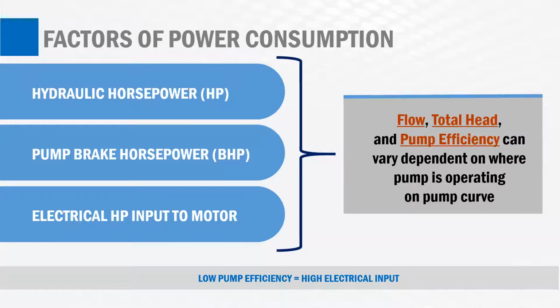So again, is the pump operating where it's supposed to be, at its operating point on the pump curve? If it's not, it might be that you have a much lower pump efficiency than you originally intended. And if that's the case, then your power consumption might be higher than you originally thought. So it's really important to look at what we call the wire to water efficiency of your pumps.